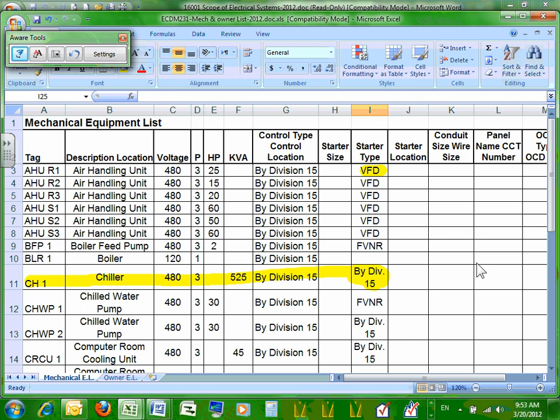Now we're seeing the chiller manufacturers build a VFD so they can ramp up the chiller more gradually, and it's less inrush on our electrical system rather than banging on a 500 horsepower motor. So they ramp it up. That's a good thing, but we're still letting it be by the chiller guys because they build it back at Carrier or Trane, and it just makes sense for them to provide it. And I would fully agree with that.